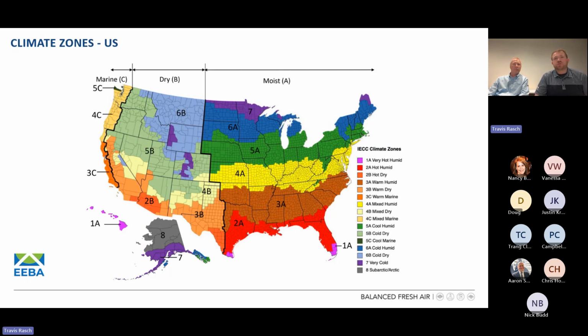When it comes to the climate zones in which we're handling these types of products, I often get asked the question, what's best in my climate zone? Is it an HRV? Is it an ERV? To be very honest, particularly throughout at least the lower 49, including Hawaii, ERVs are becoming more and more prevalent. A big part of the reason is the technology itself, the materials we make those recovery cores out of, and our ability to defrost the recovery core, particularly in very cold conditions. If an ERV is going to retain some amount of that latent moisture and we've got condensation developing within the recovery core, the last thing we want to do when we bring fresh air in is turn that recovery core into an ice cube.